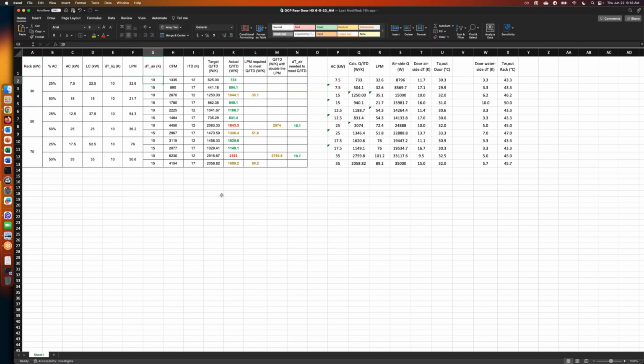There are already a bunch of takeaways we can highlight. One is that when you really start pushing the limit in terms of capacity, it becomes pretty hard for the door heat exchanger to hit the performance limits we call Q over ITD, which is the cooling capacity divided by the initial temperature difference. Sometimes even doubling the flow rate on the liquid side, it becomes a pretty big challenge.